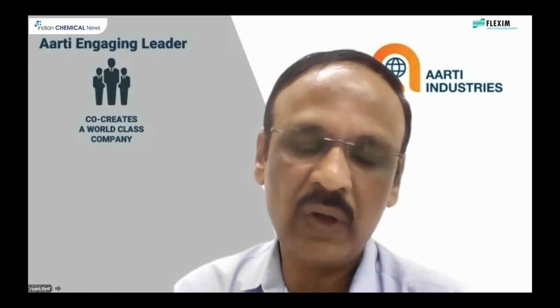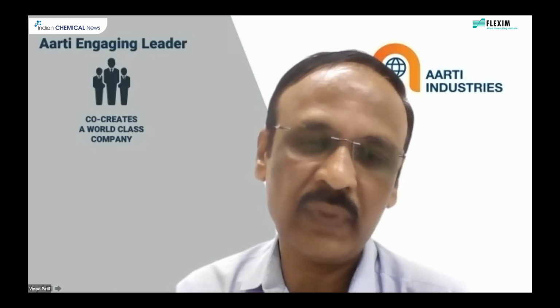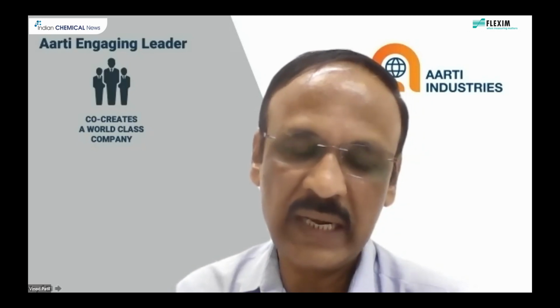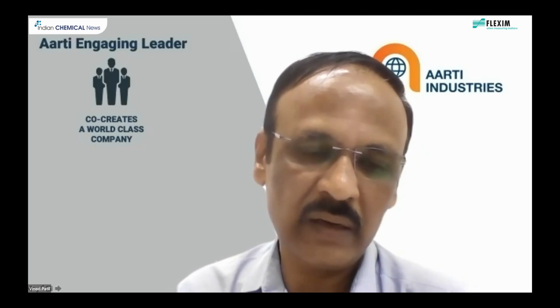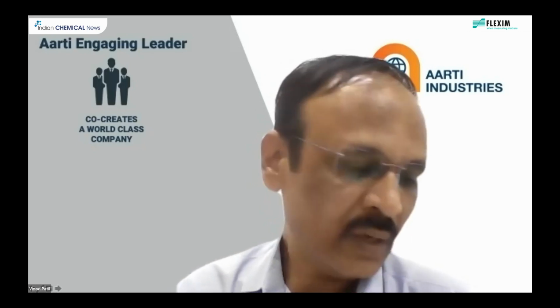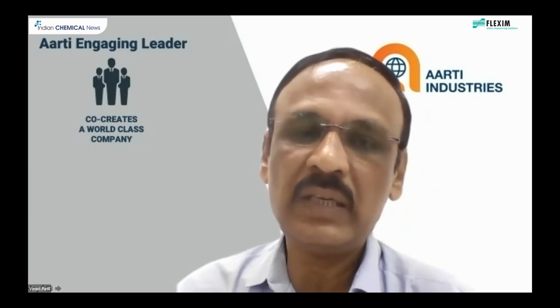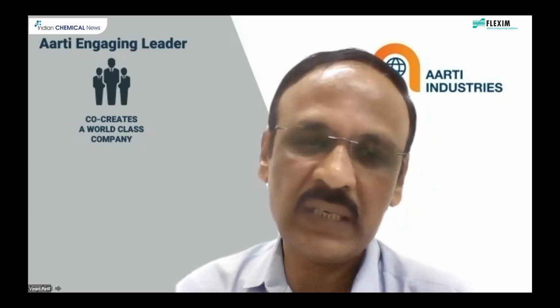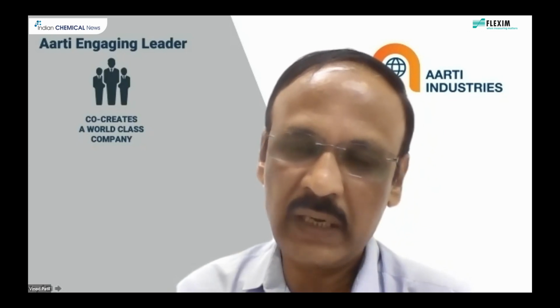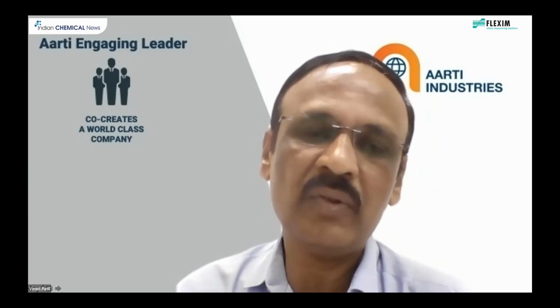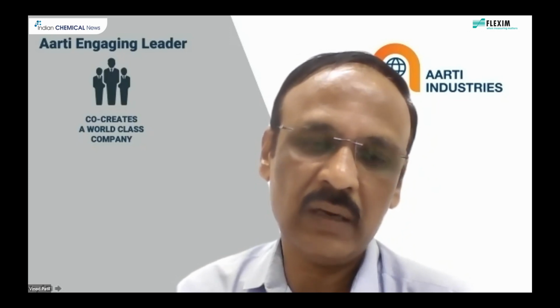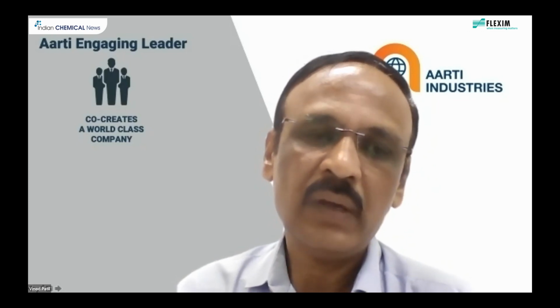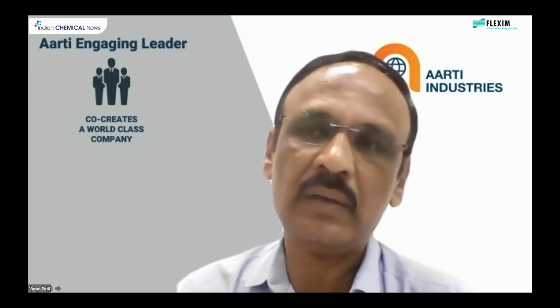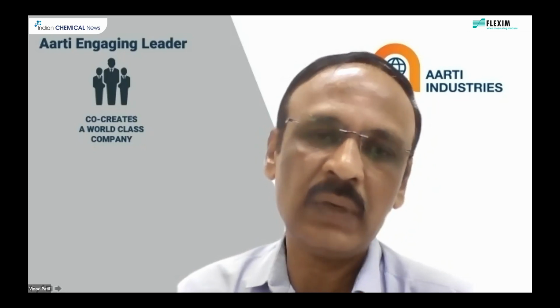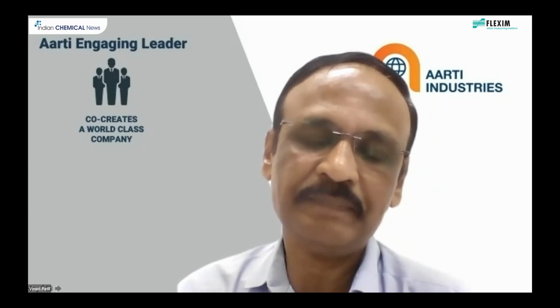So to overcome all these, the MOC challenge, the installation challenge, the maintenance challenge, there are solutions, and we at Aarti have already installed the devices to overcome these challenges. Basically for the measurement of SO3 and concentration, we have already installed the non-contact flow meters, and by installing this, we have overcome all the challenges. Yeah, Prashant.